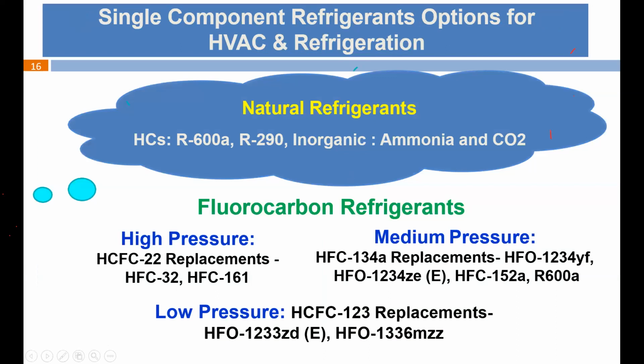Now come to what are the single-component options available globally for the HVAC and R industry. If I consider chlorofluorocarbon, this Freon, the high pressure refrigerant HCFC 22, R22, the replacement is either R32 or HFC 161. These are the replacements.